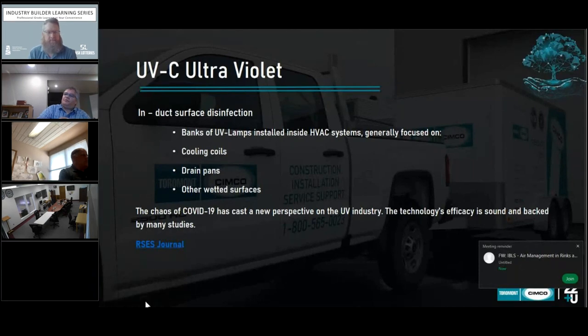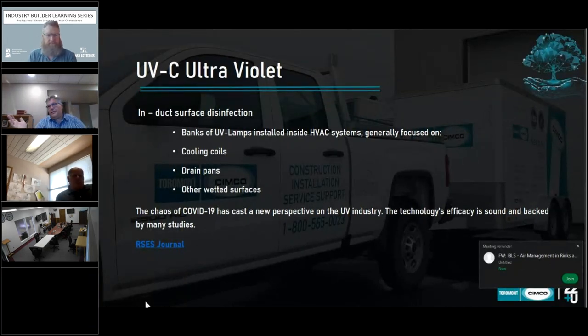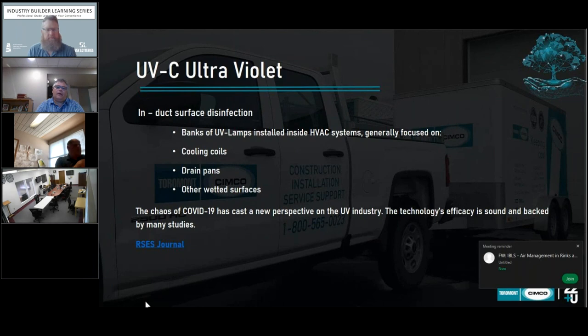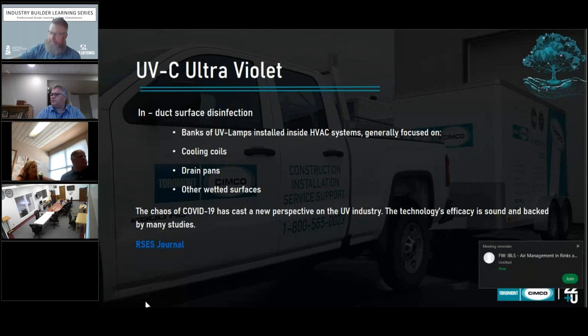For those of you with really large multiplexes, or on the other end of the spectrum with a system that does heating and ventilation for spaces and meeting rooms, you can actually use UVC right on your coils. Not only are they effective against COVID, bacteria, viruses, molds, and Legionella, UV on coils is one of the most effective ways of cleaning your coil. You can look at a potential payback of 18 months to 2 years on your investment if you're using it in this type of system.